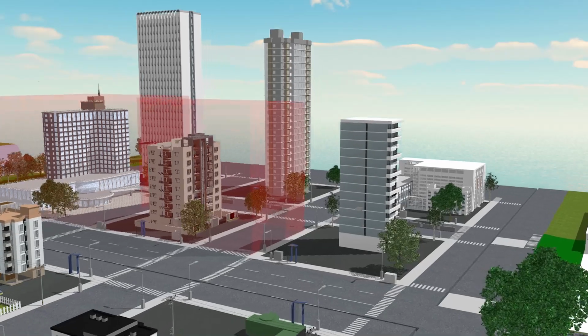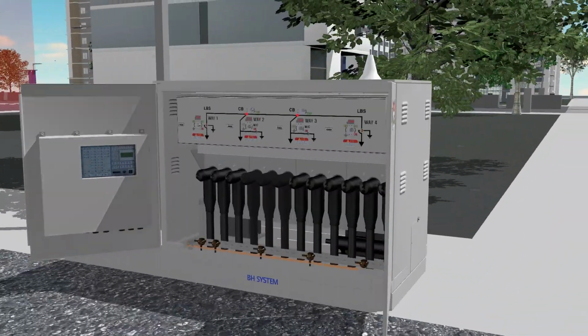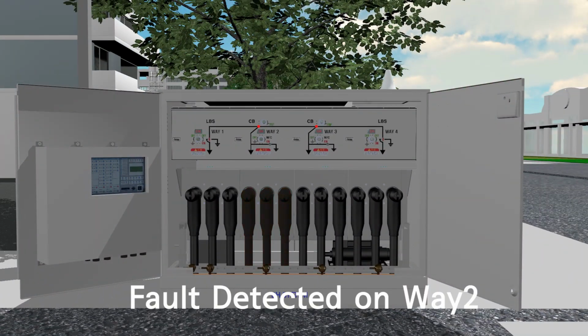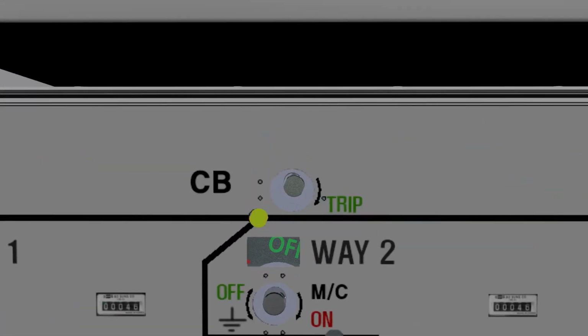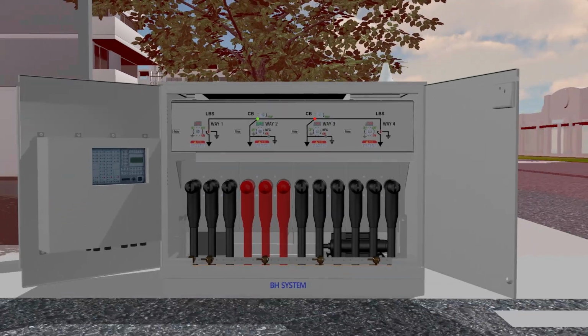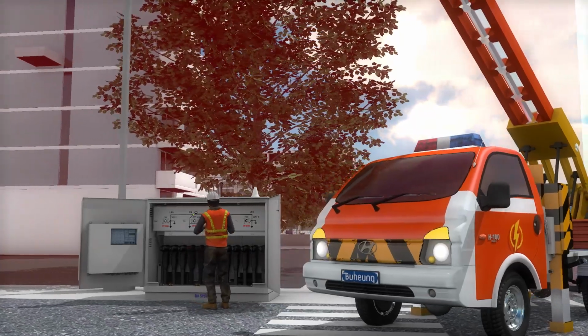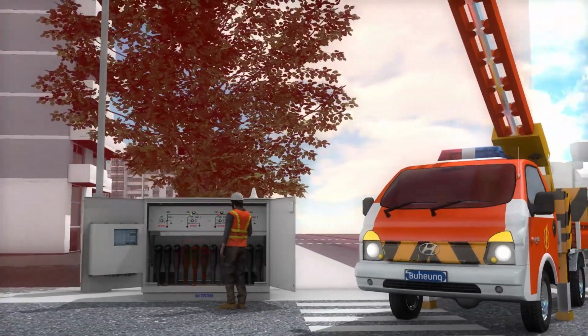The 4-way pad mount switchgear consists of Way 2 and Way 3 protected ways, and faults on the line connected to these ways are operated by single shot protection. As the pad mount switchgear trips the protected way, the healthy sections will never experience a momentary power outage caused by faults.